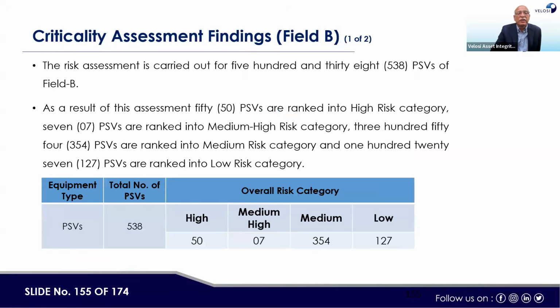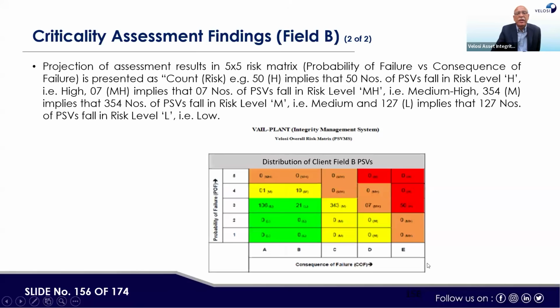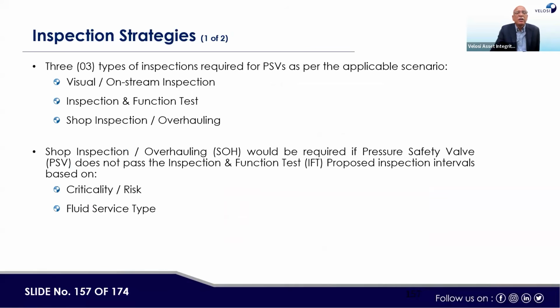Then this is the PSV for the other plant, plant B. So here 50 high, 07 medium high, 530, 354 medium, and low is 127. This is the distribution of those PSVs in the risk matrix. Then three types of inspection are required for PSV as per the applicable scenario: visual on-stream inspections, inspection and functional testing, and shop inspection overhauling. Shop inspection overhauling would be required if the pressure safety valve does not pass the inspection and function test. Proposed inspection interval is based on criticality and risk, and fluid service type.